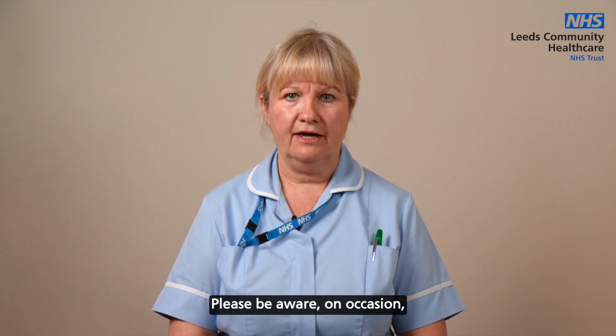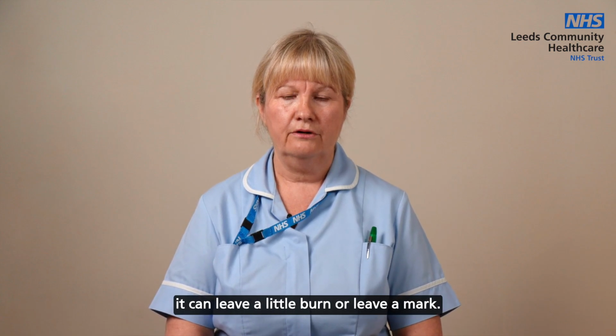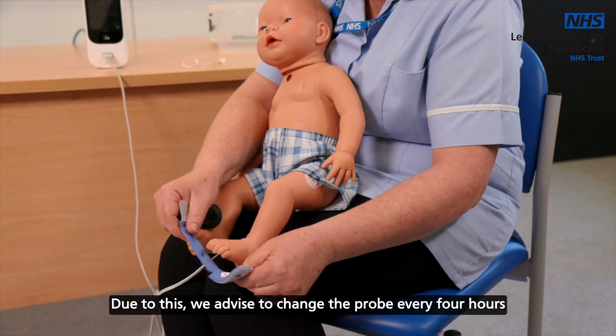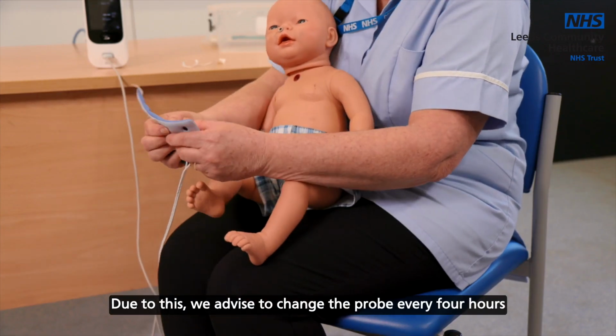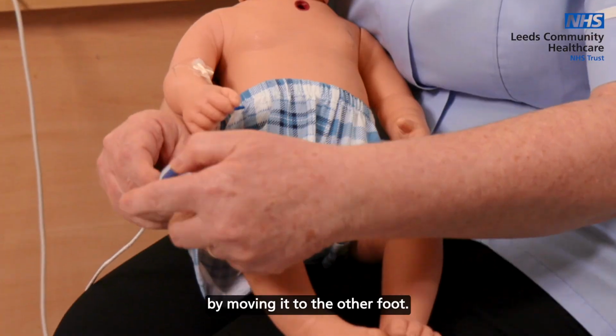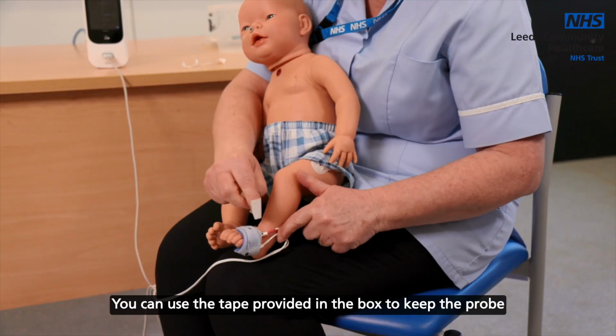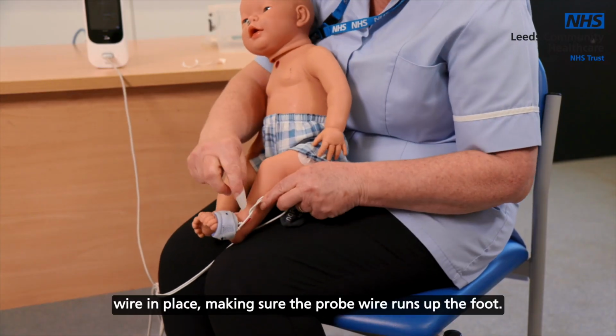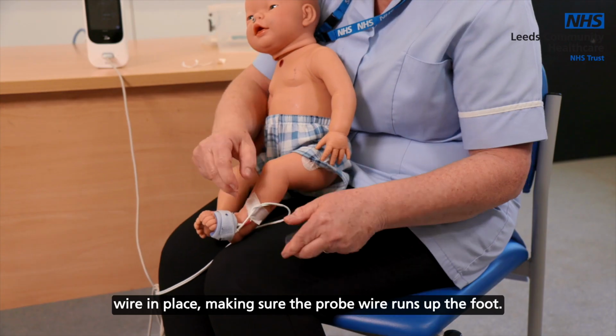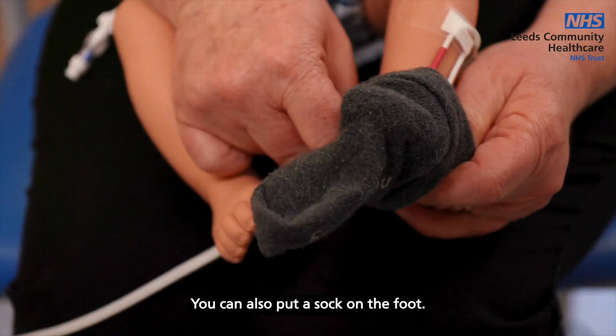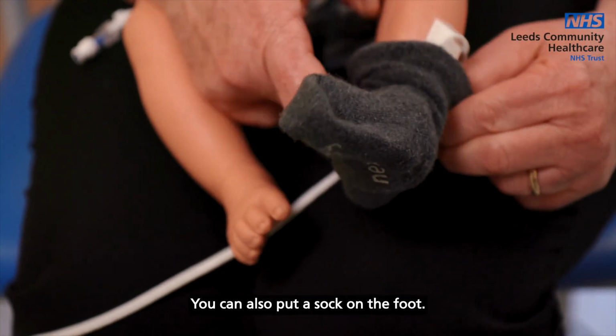Please be aware on occasion it can leave a little burn or leave a mark. Due to this, we advise to change the probe every 4 hours by moving it to the other foot. You can use the tape provided in the box to keep the probe wire in place, making sure the probe wire runs up the foot. You can also put a sock on the foot.